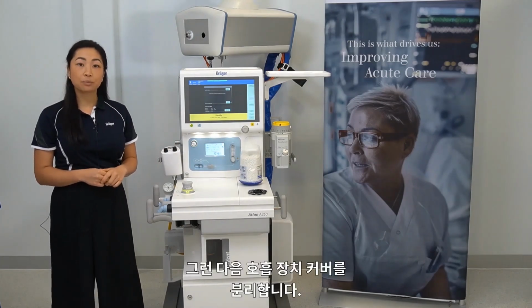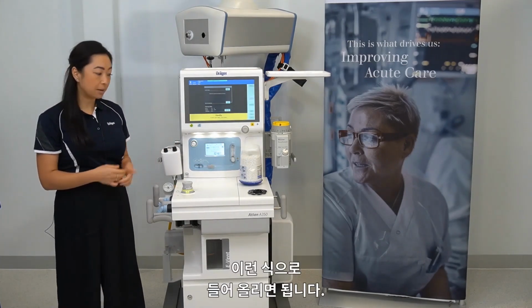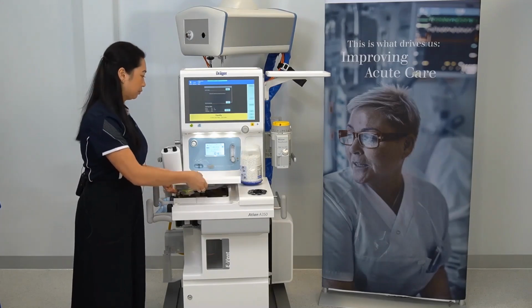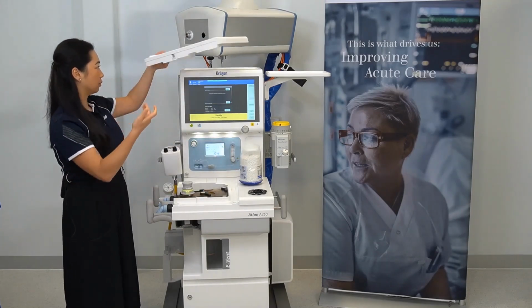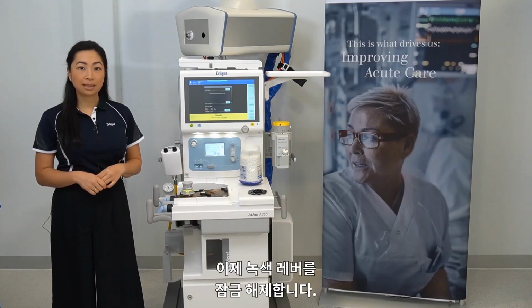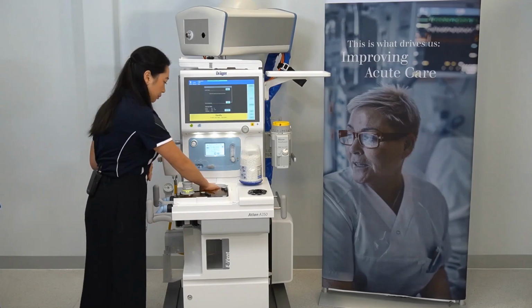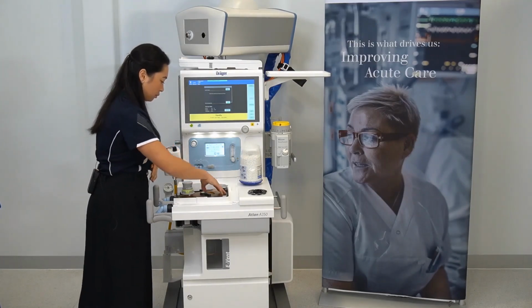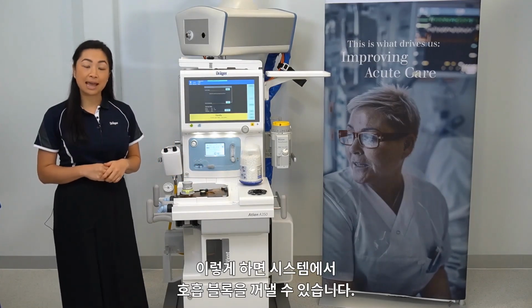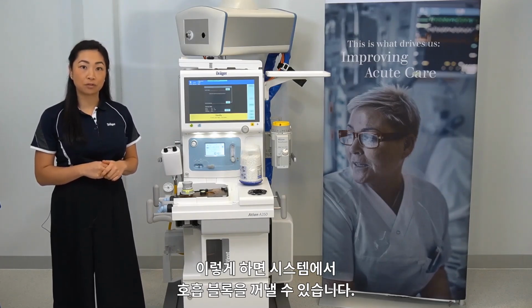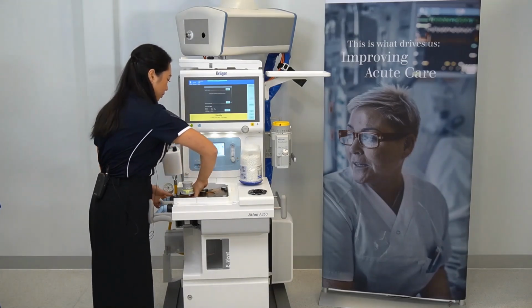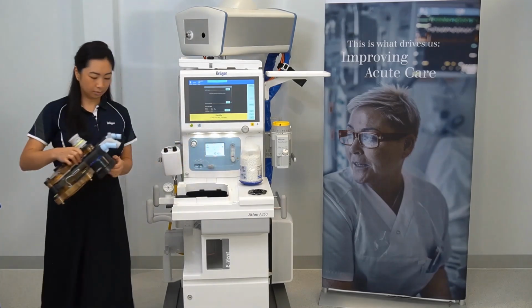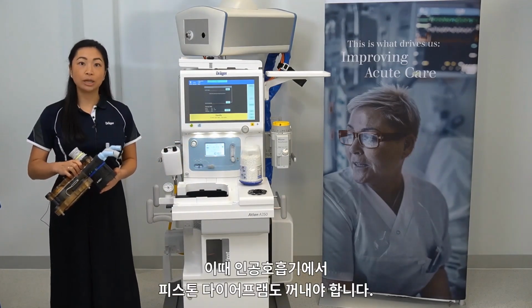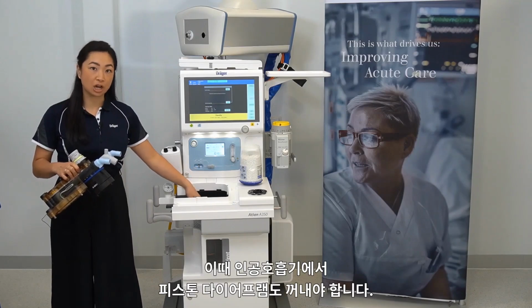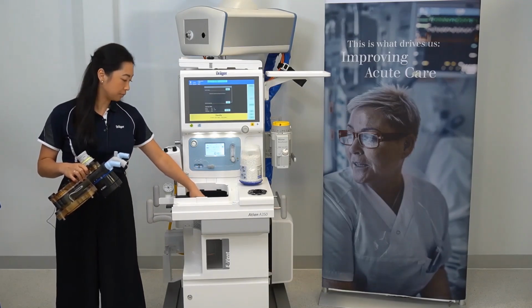Then remove the breathing system cover. This is done by lifting it up. Following that, unlock the green coloured levers. This will allow you to remove the breathing block from the system. At this point, you should also remove the piston diaphragm from the ventilator.